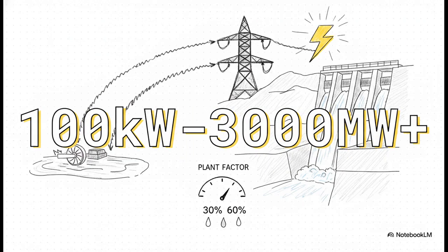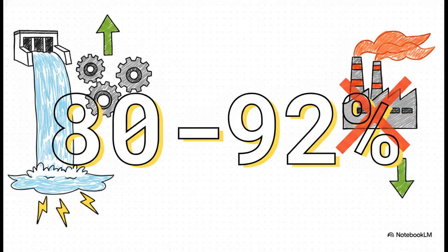Because of that incredible drop and discharges that can range from 1 to 10,000 cubic meters per second, the power output is wonderfully scalable. A single project's output can range from a localized 100 kilowatts to a staggering 3,000 plus megawatts for one of those massive grid-anchoring dams. Generally speaking, these operate with a plant factor of about 30 to 60%, heavily depending on the seasonal availability of water. Now, these numbers right here reveal exactly why hydroelectricity is so vital to our overall energy mix.